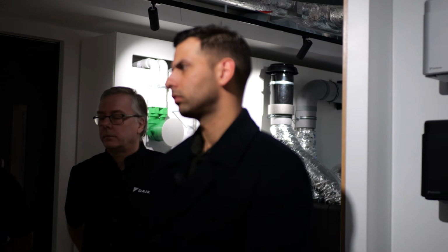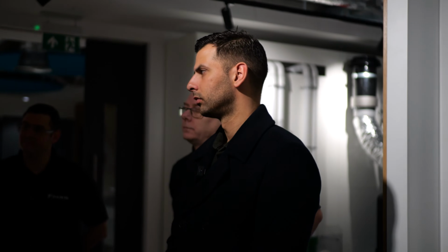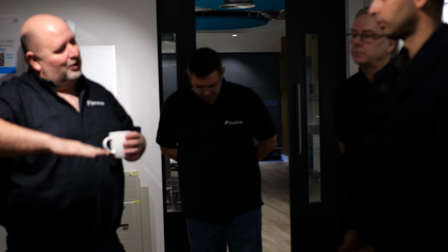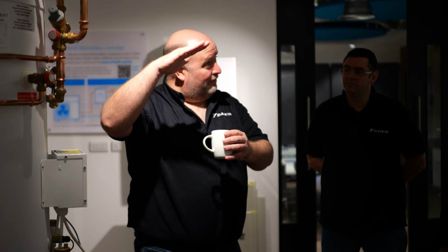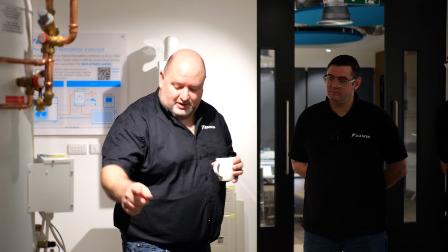If there was an issue with the heat pump, it can use the backup heater. It's mainly there for defrost and minimum water temperature. Depending on the glide of the refrigerant, generally the higher the flow temperature the refrigerant can handle, the higher the minimum water temperature it needs before you get full output from the heat pump. You've got that glide, haven't you? So the backup heater will generally be used within the lower water temperature range, whereas this, in combination with that buffer, means we can get it up to 37 degrees C before it starts heating up.